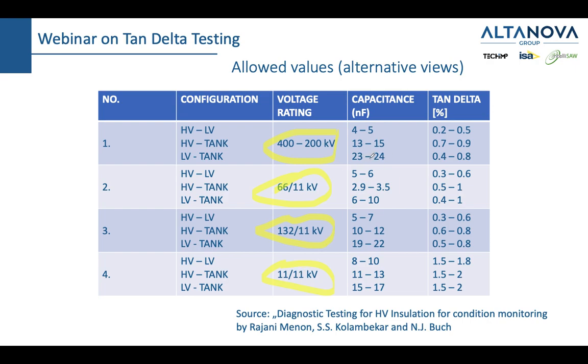So we could say that there are different tan delta values for these transformers. So for example, what you can see here is that the values for extra high voltage go from 0.2 to 0.9. And I want to turn your attention to one more thing. You see that here we don't talk about only one number. We have three values which we will be talking about. Because we have an insulation between high voltage and low voltage. We have insulation between high voltage and tank and low voltage and tank. And you will see later what I mean by this.